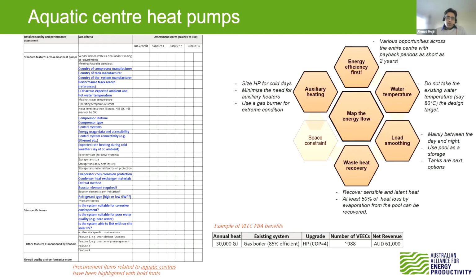There are lots of opportunities for waste heat recovery in an aquatic centre, which we've covered in the guide. One important point is that there's a huge amount of latent heat in the exhaust air from aquatic centres. Analyses have shown that at least 50% of the heat lost through evaporation from the water's surface can be captured by heat pumps, since they can condense that moisture and capture its latent heat.